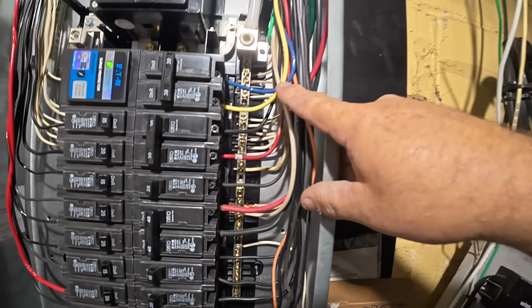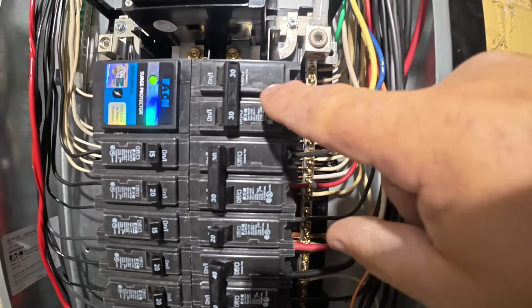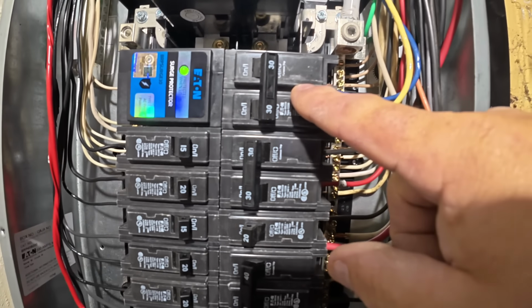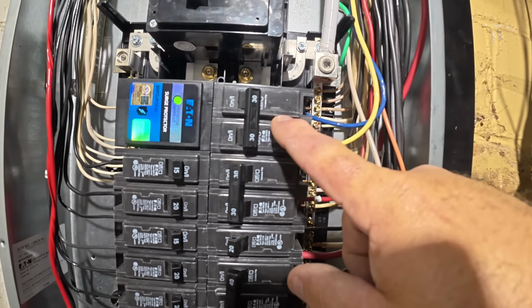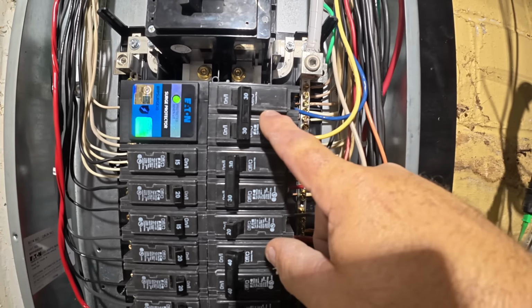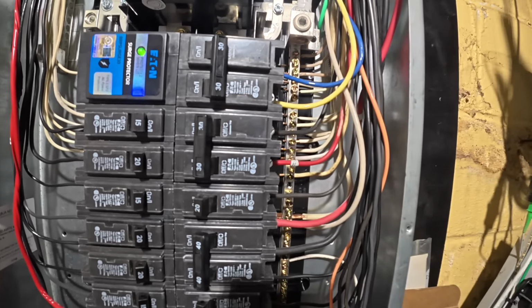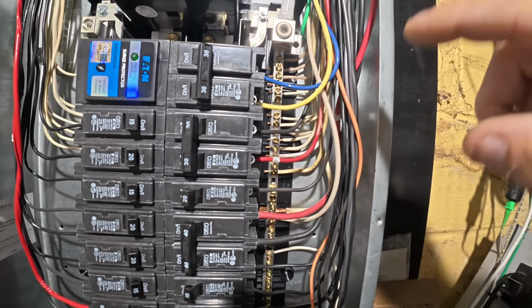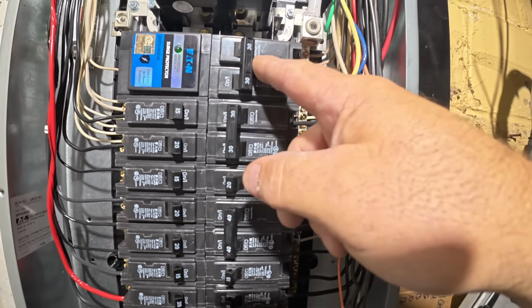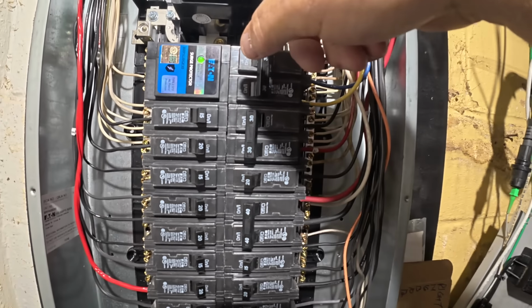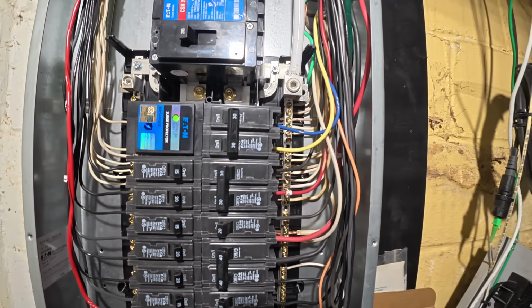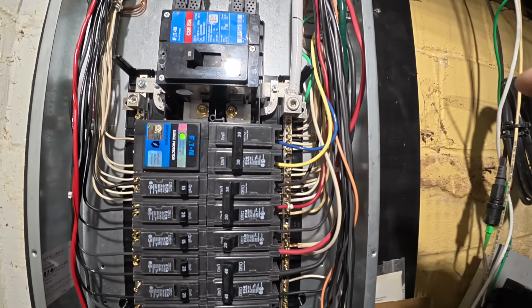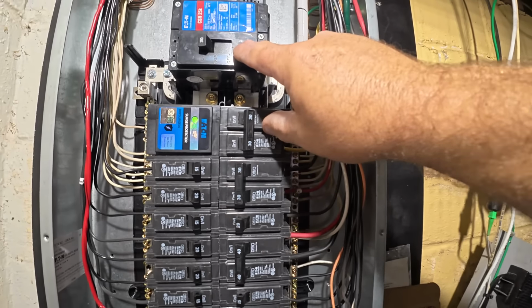Okay, so as you can see here, the yellow and blue conductor attached to this 30 amp circuit breaker that is off. The idea of the interlock is so that this 30 amp circuit breaker does not supply power to the inlet outside. All right, the interlock, you won't be able to turn this on unless the main breaker is off. This way you won't backfeed the panel from the generator. That's the whole purpose of the interlock.